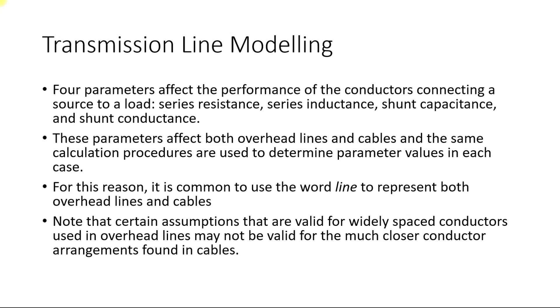These parameters affect both overhead lines and cables, and the same calculation procedures are used in each case. The difference lies in the values. In a cable, conductors are in close proximity with a better insulator such as rubber instead of air. This increases the capacitance value significantly, so cables have much more shunt capacitance than overhead transmission lines.